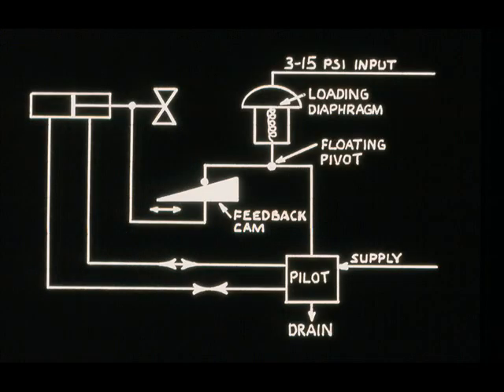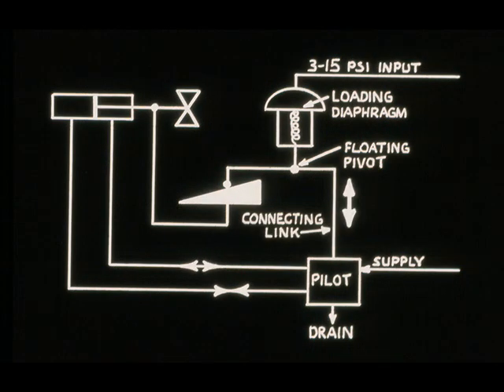This is a schematic representation of the system. Is this a motion or a force balance principle? It is motion balance because the feedback is derived by direct mechanical means. A feedback cam is tied directly to the valve stem.